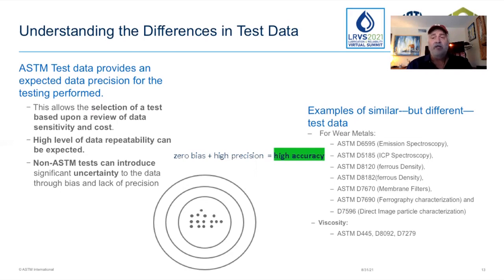So I'll use viscosity as an example. The standard viscosities are really, really precise, and it can be measured in terms of tenths of a centistoke. That's pretty accurate. And one could argue for many condition monitoring applications, more accuracy than we really need. There are other viscosity test methods which are not that accurate, perhaps 2 or 5 or 8% with a plus or minus.